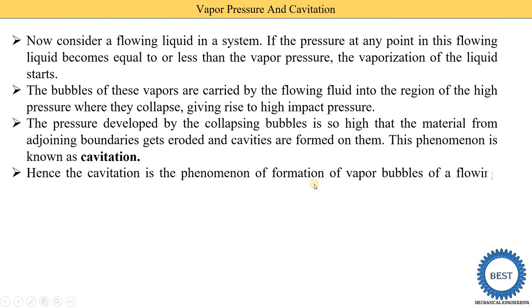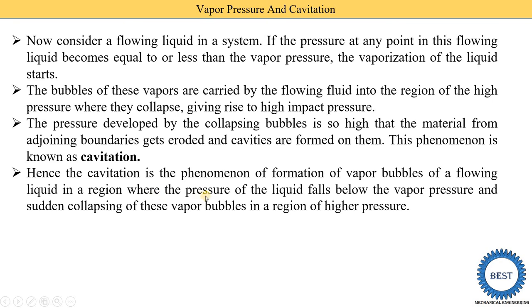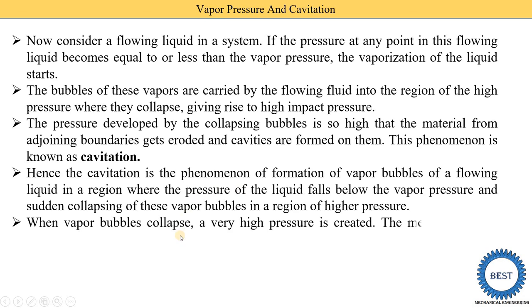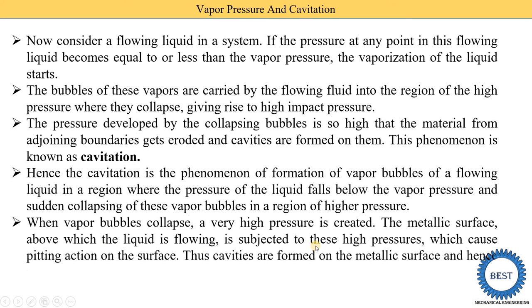Hence cavitation is the phenomenon of formation of vapor bubbles in a flowing liquid in a region where the pressure of the liquid falls below the vapor pressure. The vapor bubbles are created in the low-pressure region, flow with the fluid, and reach a high-pressure region where they suddenly collapse. When the vapor bubbles collapse, very high pressure is created and the metallic surface is subjected to this high pressure, causing a pitting action on the metal surface, forming cavities.